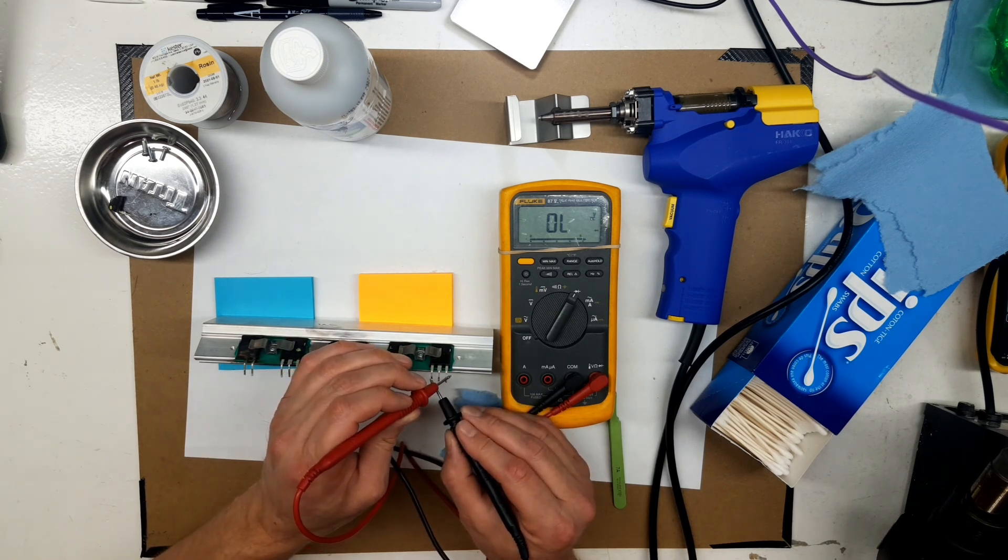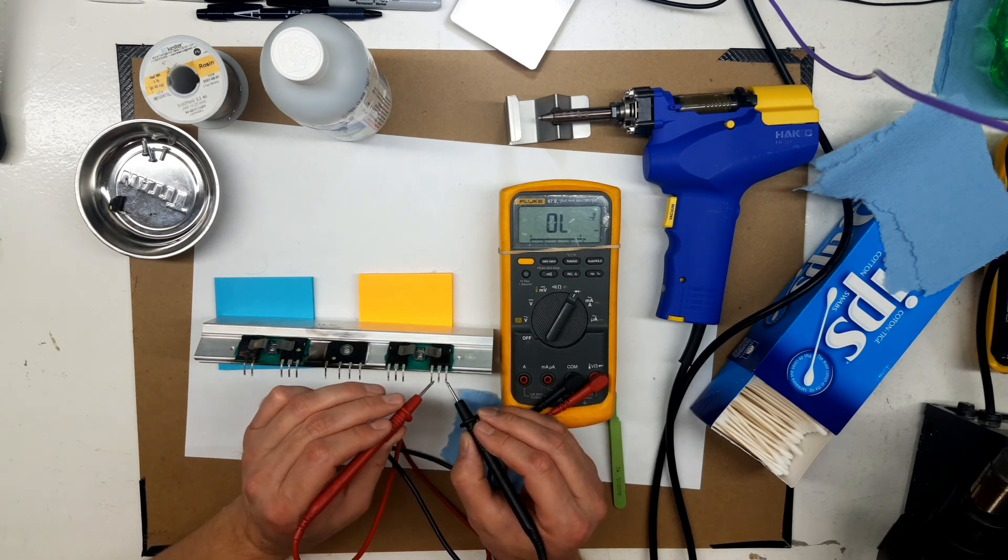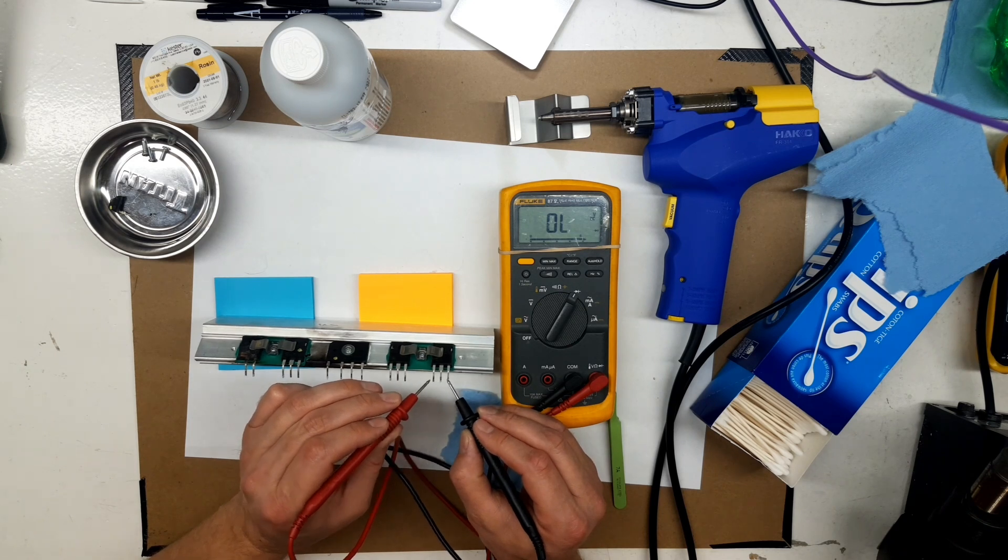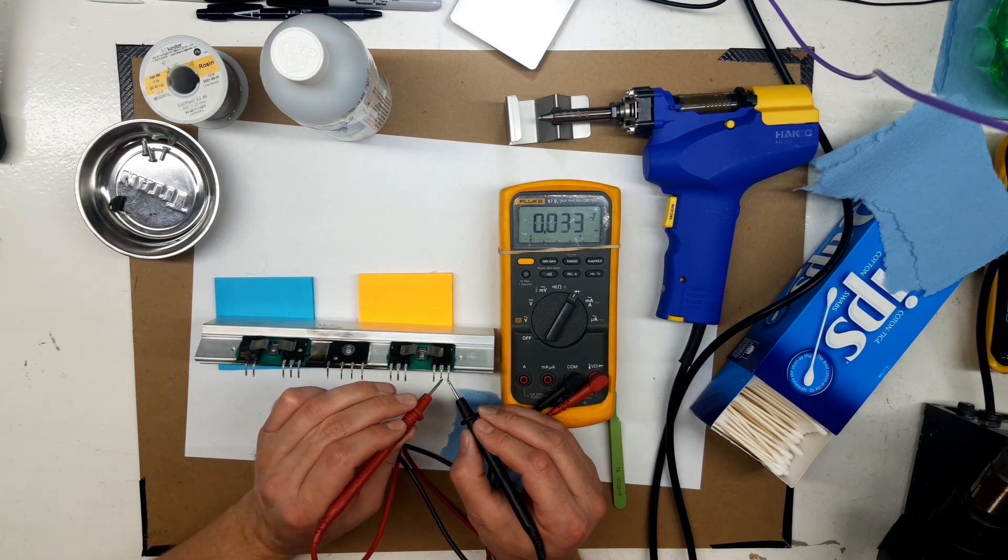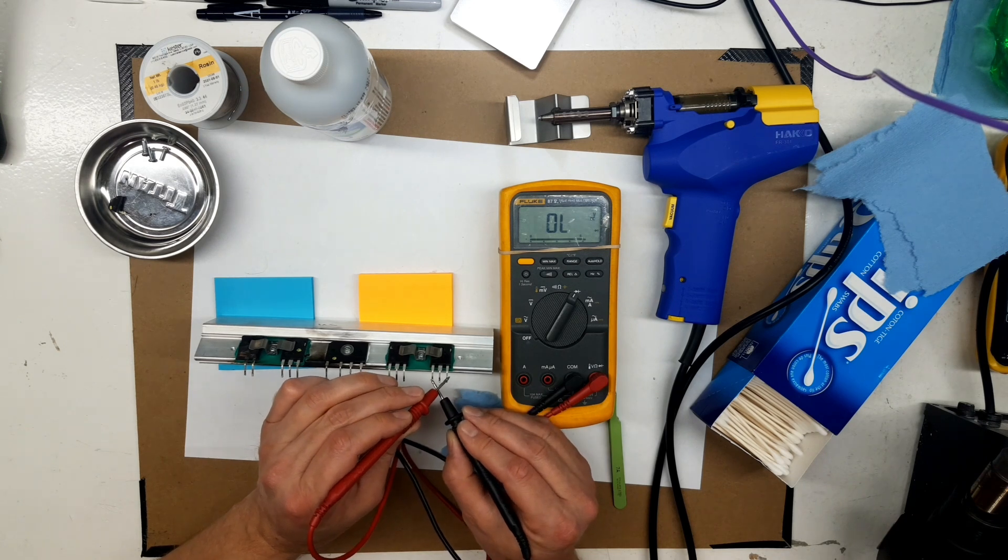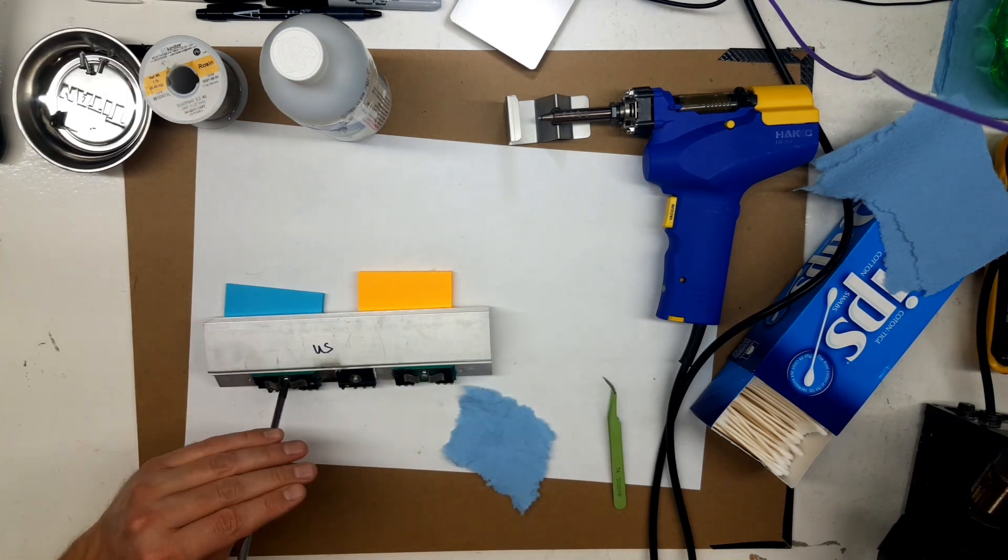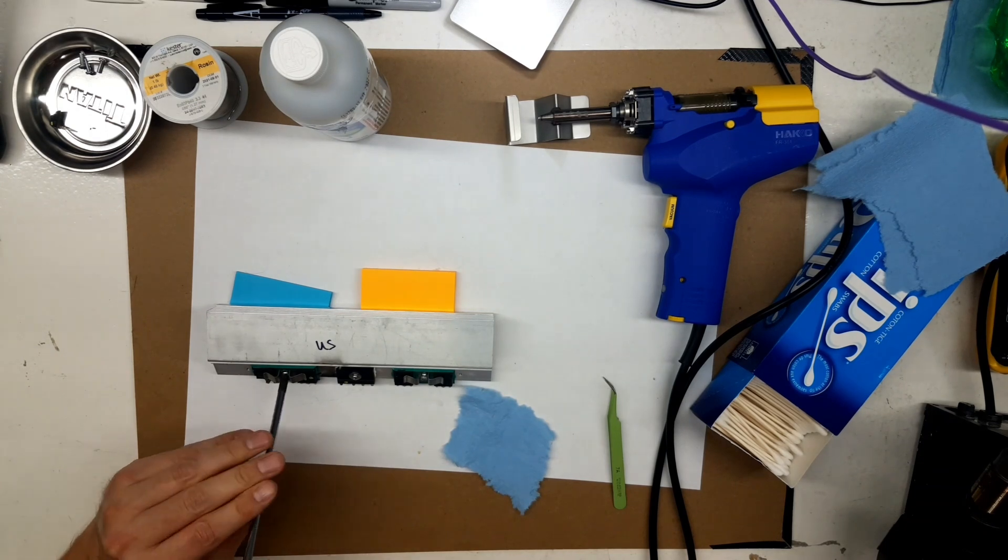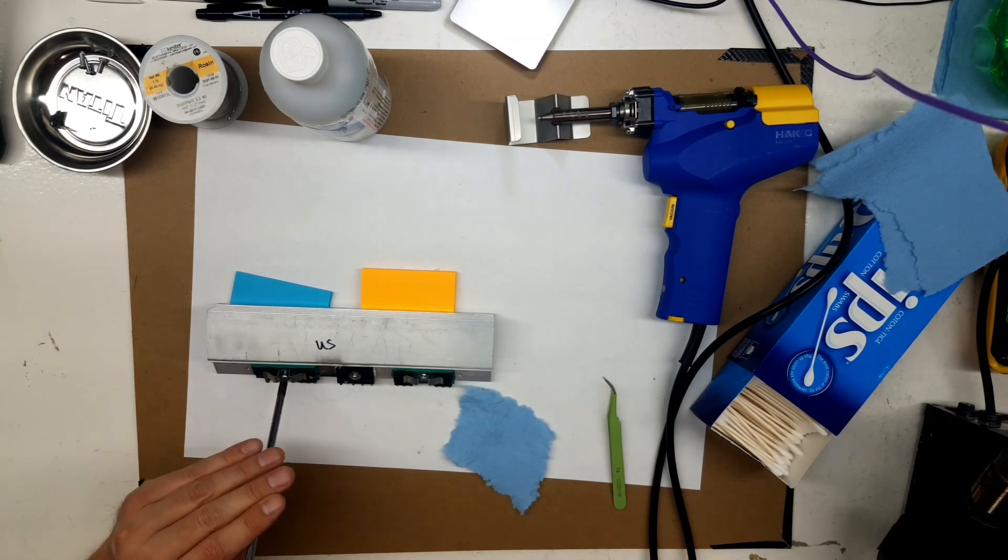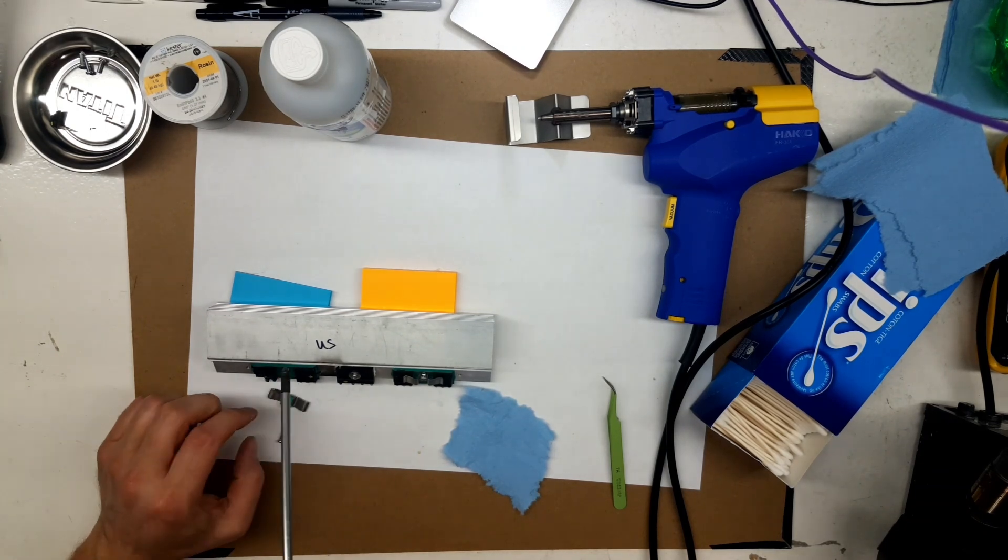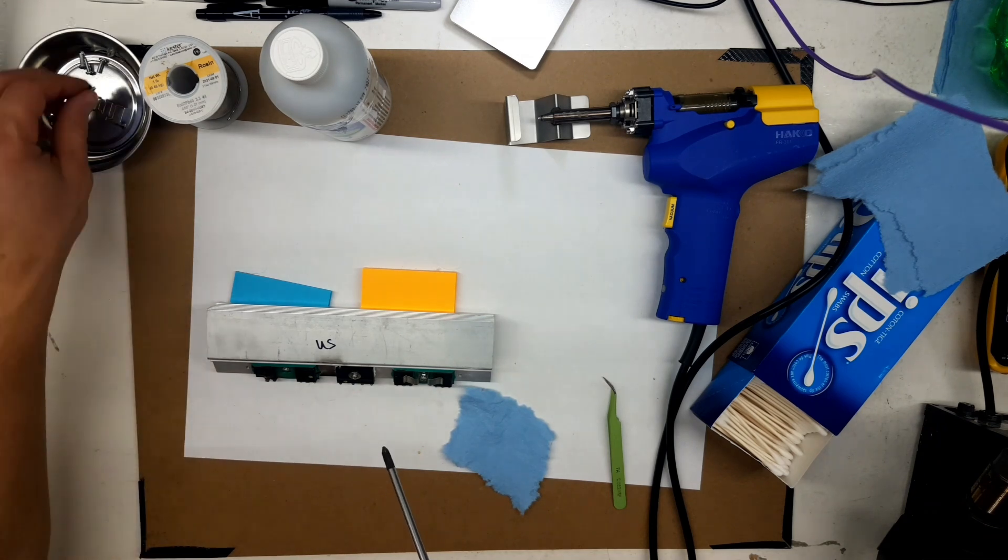I'll manually turn it off. Test collector to emitter. Should be no conduction. Now I'll turn the gate on. Now I'll test again. There should be conduction. Turn it off. Test again. So both the ones on the right turn on and off. So they're probably still good. And we tested the body diodes. And they're still good, too.